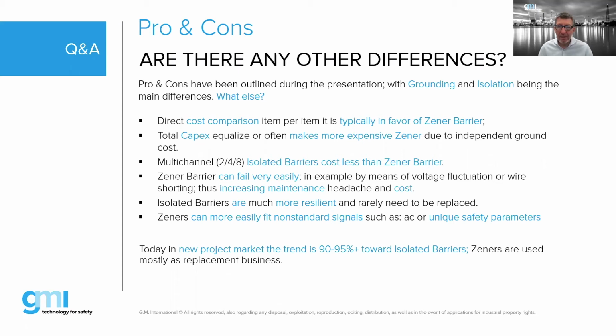We have a lot of live questions here. Let's see if we can answer some of them. To power an IS instrument, do we require an IS power supply, or can it be powered using a normal power supply in between an IS barrier? The barrier itself can be powered by a normal power supply, right? Correct. But you cannot send power into the hazardous location with a normal power supply. GMI makes power supplies that are IS, with intrinsic safety incorporated. But beyond the barrier, between that associated apparatus and the field device, there really shouldn't be any other devices other than your cabling and interconnects, maybe marshalling boxes, junction boxes, and things like that.